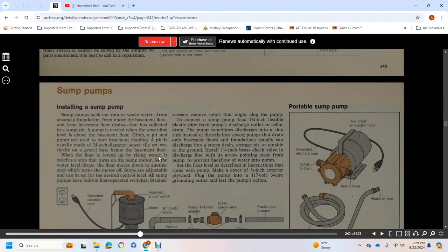When the float is forced up by the rising water, it reaches the stop that turns on the pump motor. As the water level drops, the float moves down past the stop that turns off the motor. The stops are often adjustable, so they can be set to the desired control level. All sump pumps are built with float-operated switches, strainers, and screens to remove solids that might clog the pump. To connect the sump pump, lead a 1.25-inch flexible plastic pipe from the pump discharge out to the cellar drain. The pump sometimes discharges into a slop sink instead of directly into the sewer. Basement floor foundations can usually discharge into the storm drain, the seepage pit, or outside to the ground.